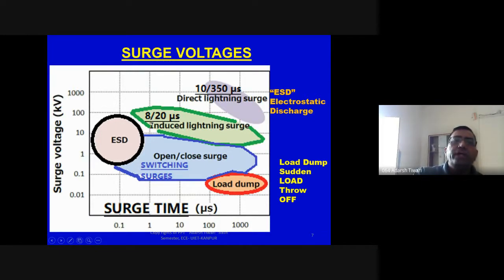So what is this 8 by 20 or 10 by 350? The first number is the rise time of the impulse, and the second is the fall time. So if we say 10 by 350 microsecond, that means the pulse rise time is 10 microsecond and the tail of that pulse is 350 microsecond.